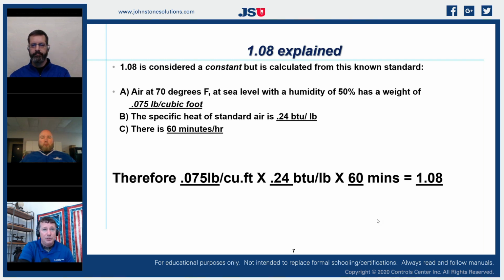So if we were using this in a controlled environment, say we were working in an electronics lab that had an air handler that was remote to that room, and in that electronics lab, it was an oxygen-free lab that was nitrogen filled. Our weight of that air is going to be very different, and then we would have to recalculate it. But that's all we do. We just recalculate what the actual weight would be, what its heat transfer would be, the BTUs per pound, and now we can come up with a different number.